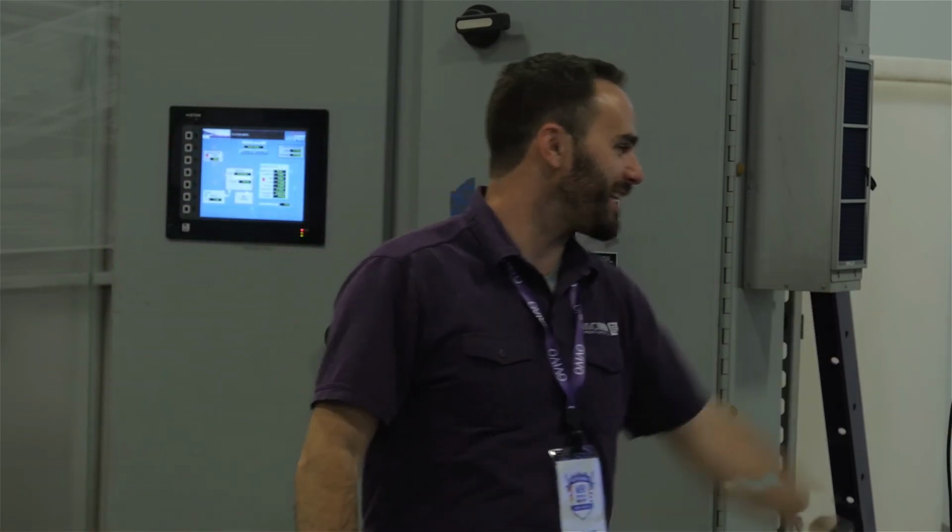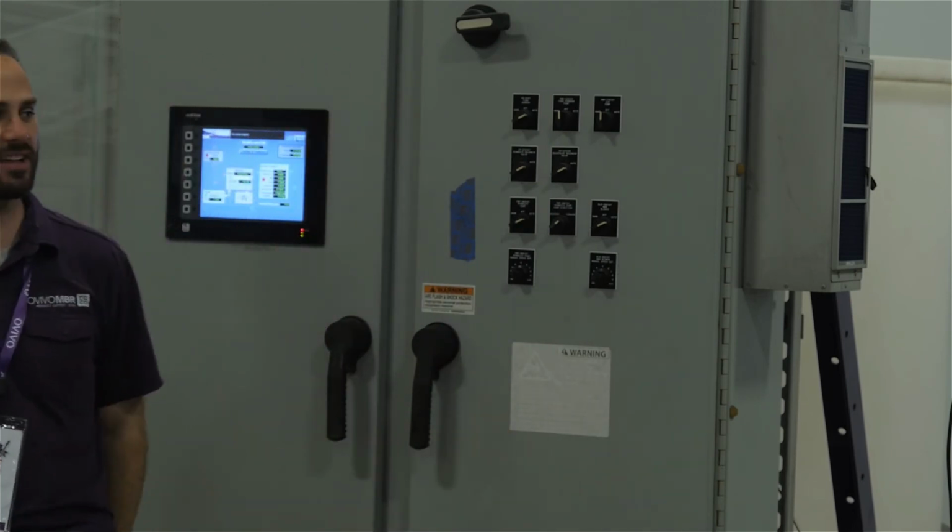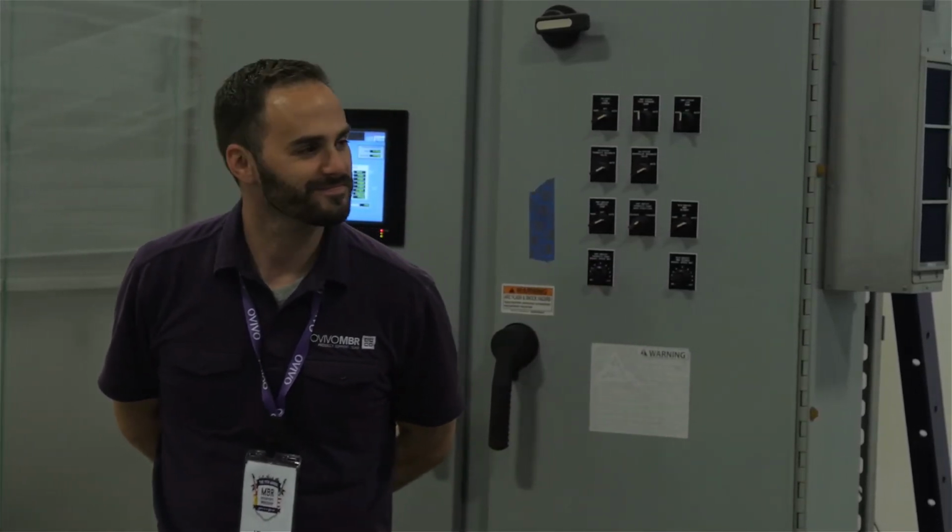Okay. Number 3 is how can the bubbles impact instrument readings and PLC calculations? Supposed to be running a flow of 100 GPM, will or will not? Your flow and pressure affect your transmembrane pressure calculation, so what do you think your value is? TMP is off. TMP is artificially inflated. So, that's exactly what it is.